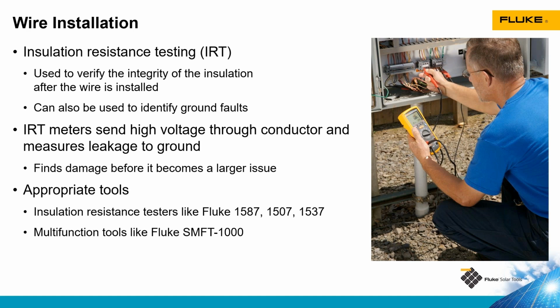It'll also do a unique test where it will take the positive and negative conductors in the PV source circuit, short circuit them together internally in the tool, and then measure the insulation resistance of that short circuit to ground. What that does is eliminate voltage potential between the positive and negative conductors and ground, and gives you a little bit safer and more accurate test.